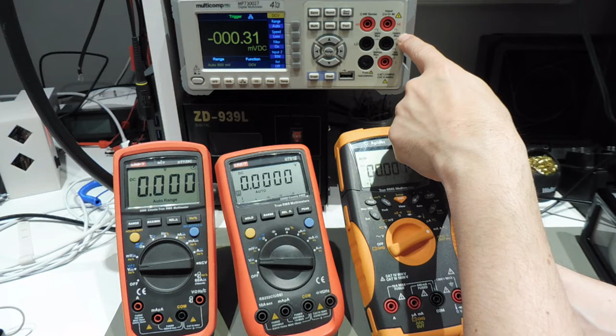This bench meter here tells you it can measure up to 1000 volts. Okay, that's important. It has this additional information here that the ground terminal cannot be more than 500 volts away from the actual protection or earth protection of this meter, which you usually should not reach, but it might happen. This could kill this meter. And the second important thing, and that's not mentioned here, is that in AC mode it's still 1000 volt maximum, which means that you cannot measure more than around 700 volt AC voltage, because the peak of such a voltage will be 1000 volt.